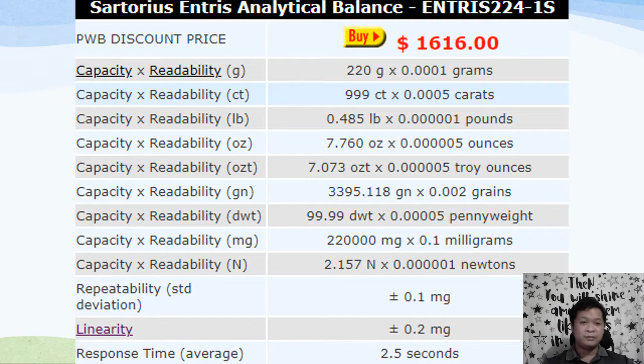Also, we also have the average response time for a balance. No? Kasi kung marami kang tinitimbang, ayaw mong mag-antay ng matagal para lang mag-equilibrate yung balance mo kasi that's time lost. No? Especially if you're weighing things in succession and things that, let's say, out of the oven, out of the desiccator, you have something you need to weigh and it absorbs moisture the longer you put it out in the weighing pan. No? So you'd want something with a fast response time of, well, maybe less than 5 seconds. So I am not sure if you were able to encounter something like this in your maybe high school. Kami nagamit pa namin to sa FS106 noon. It's not digital, but it's pretty good for certain uses. No? At kahit brownout, magagamit mo siya.